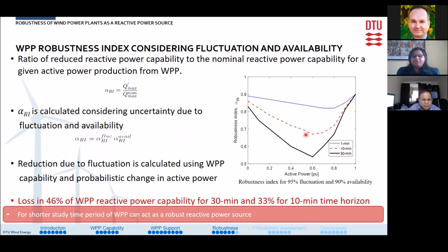Here is an example of the robustness index, which is calculated with 90% availability and including 95% of wind power fluctuations. We can see here that the robustness index is decreasing with increase in time period of study. And in case of a 30-minute time period, we see that around this 0.6 pu active power, the robustness index is around 0.54, which means there can be a loss of up to 46% of wind power plant reactive power capability in case of a 30-minute time period. Similarly, in case of a 10-minute time period, we see that there can be a loss of about 33% of wind power reactive power capability.